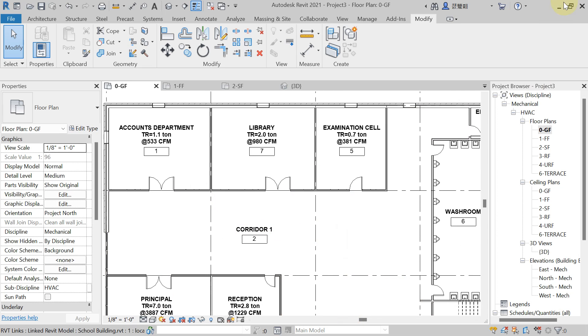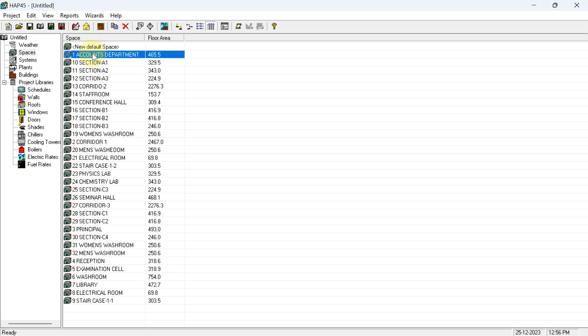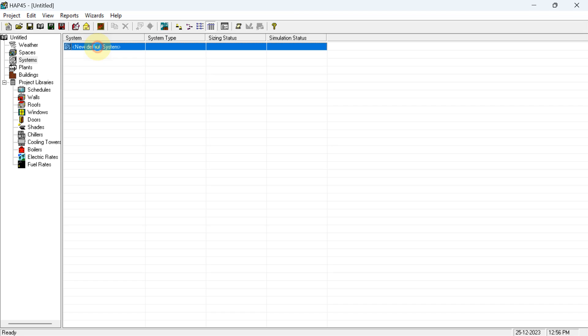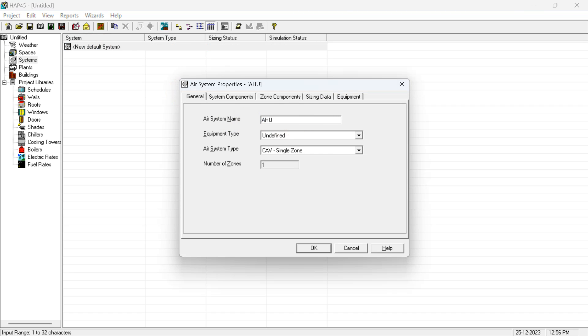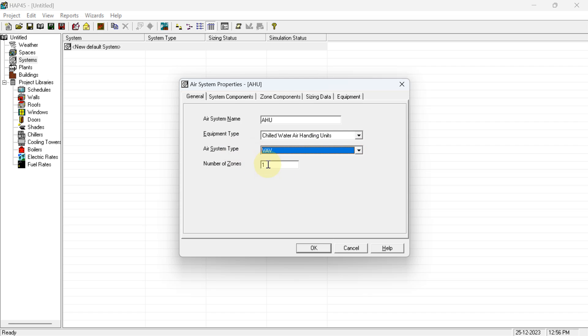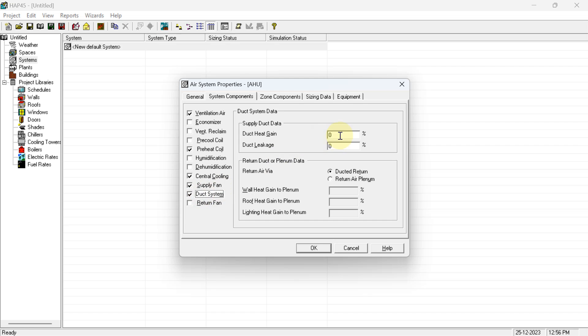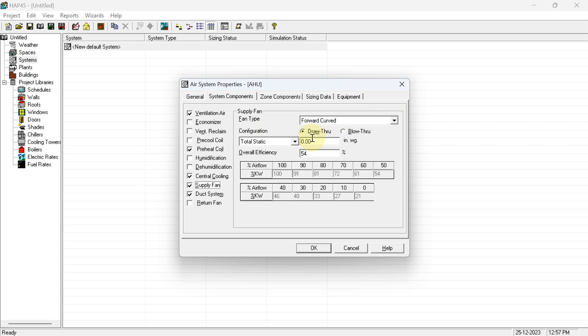Open your floor plan to check the results from HAP. In the system, select New, then Default System. We are using an AHU, so name it 'AHU Equipment' — a chilled water air handling unit with a VAV system. Select one space for account department. In the second system component under duct system, take 10% heat gain and 5% duct leakage. Return air is going through ducted ducting. In the supply fan, select the fan type with total static configuration — two-inch water gauge.